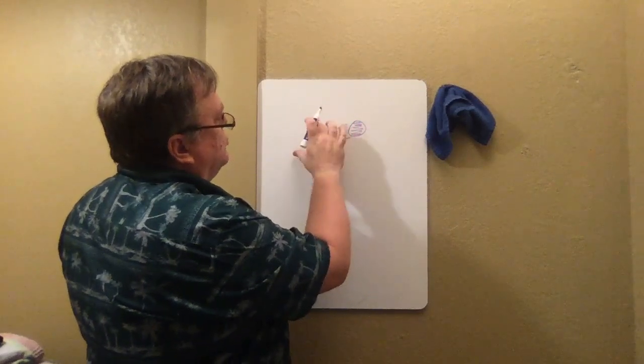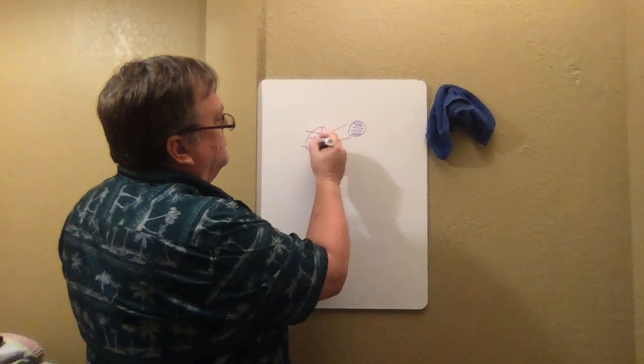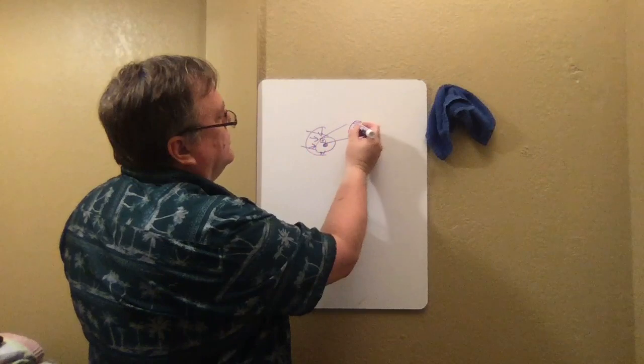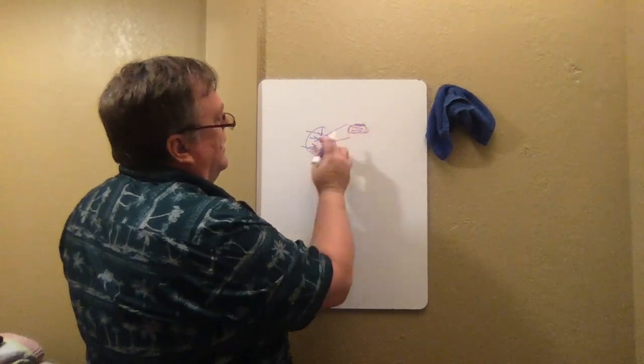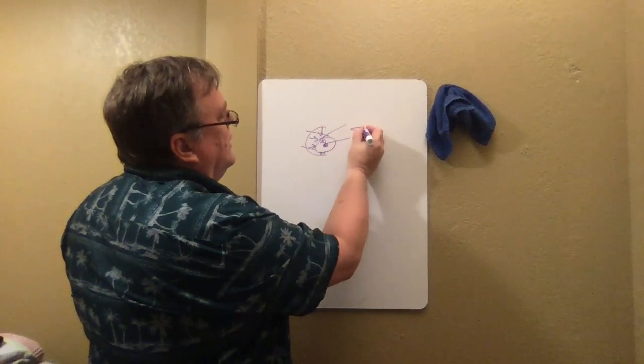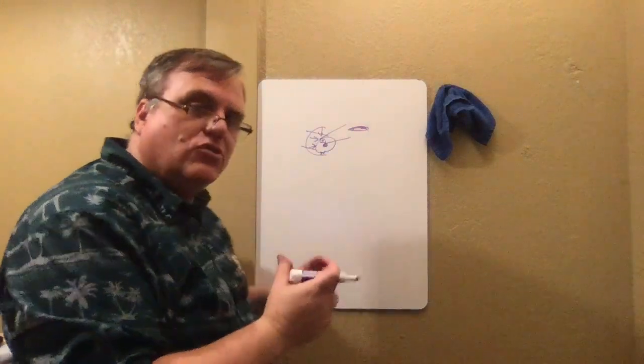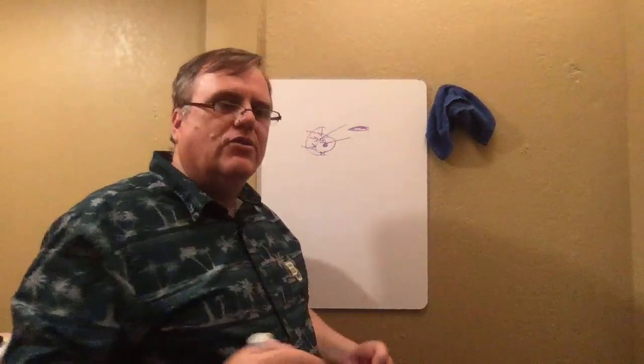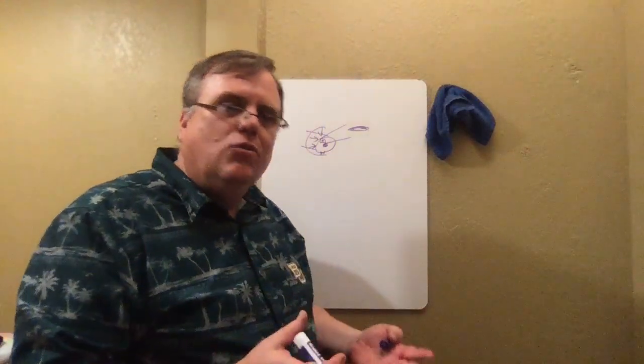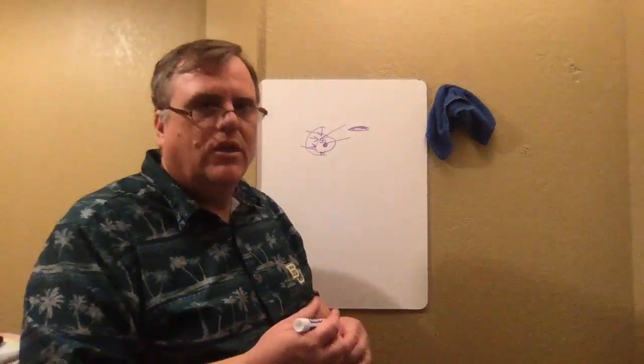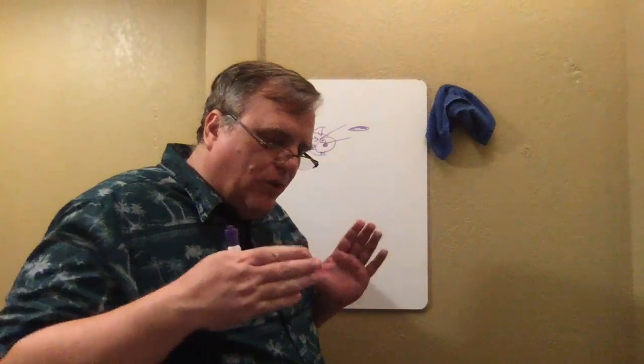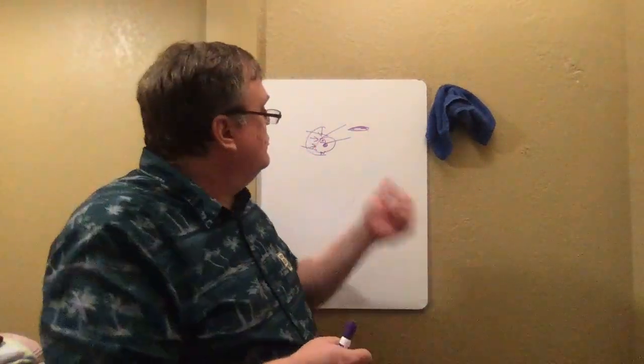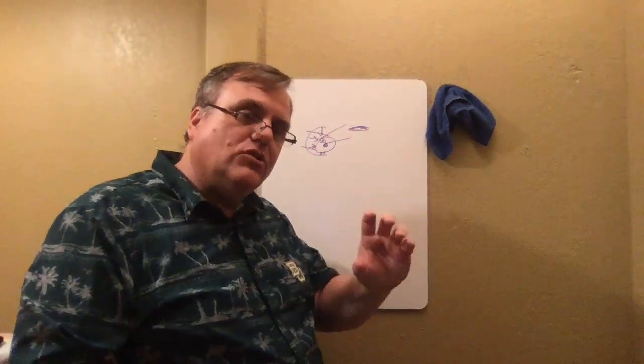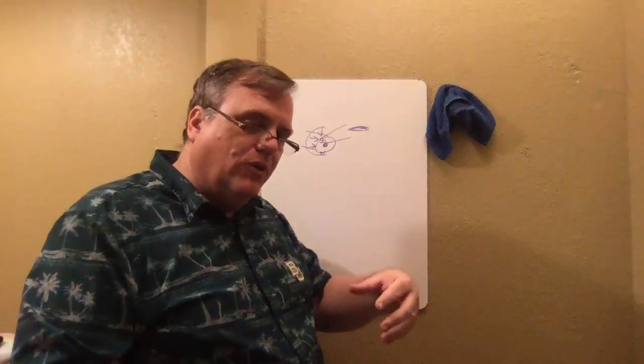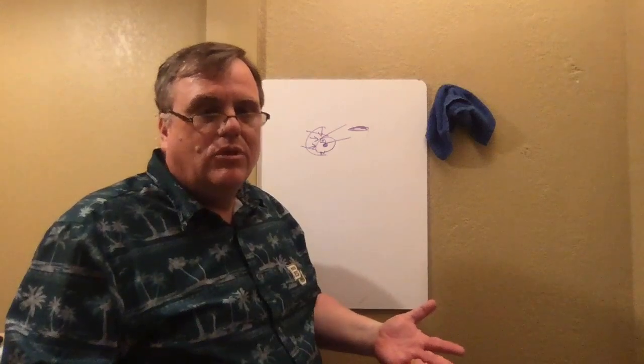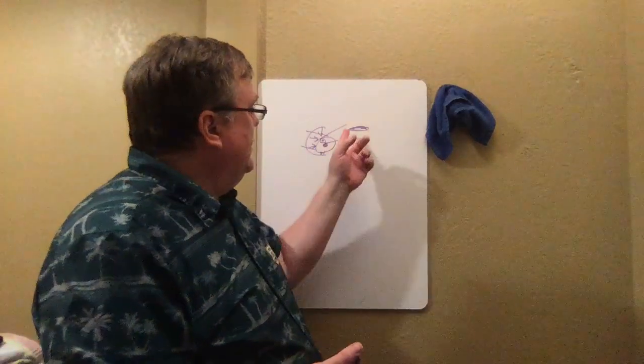As you constrict the person's arm with the cuff, it's pressuring in on all sides and it's going to squeeze the blood vessel. As you keep adding pressure, it squeezes and squeezes, and eventually it seals it up so that no blood flows. As it starts squeezing, the blood has to flow a little faster to get through there, and so it makes a characteristic noise. They call it a sputtering noise, or however you want to say it. As it's flowing through, they can hear it. Before it starts compressing anything, there's no real sound. As it starts compressing, sound starts. Once it fully compresses, there's no longer any fluid flow, so there's nothing making sound. At that point, the sound shuts off, and that's how they can tell that they're above it.